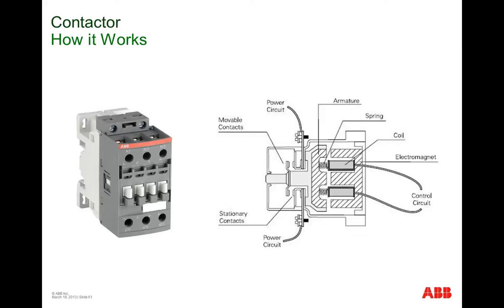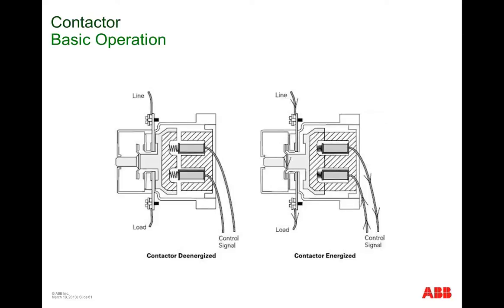And this is more or less the form of a relay, but it controls an electric motor. The power to the electric motor flows through this power circuit on the front here, and typically this is 460 volts, three-phase AC current. There's a series of contacts in the front here that open or close to turn the motor off and on. In the back of the contactor would be an electromagnet that's powered up through a control circuit that's 120 volts AC in nature. A push button would control this. So basically we're isolating a human touch at the push button level from the 460 volts, which is more hazardous at this level here. So one of the functions of a contactor is to isolate a human operator from a higher voltage motor circuit.